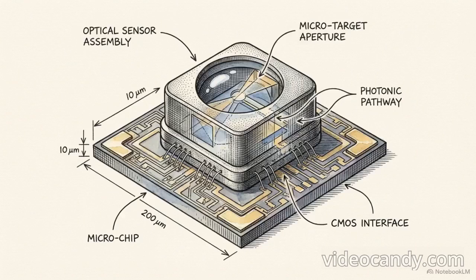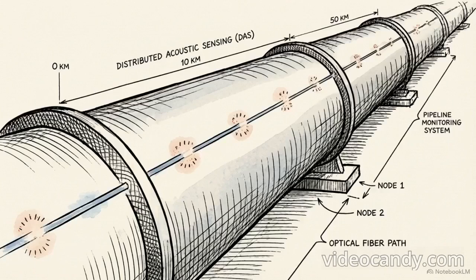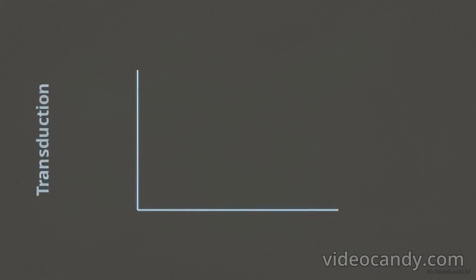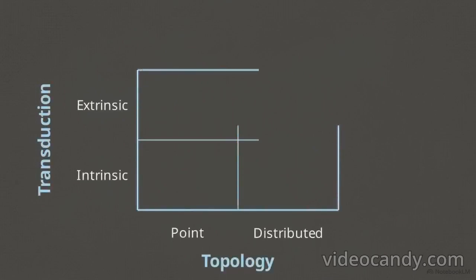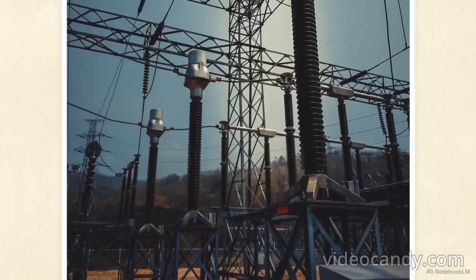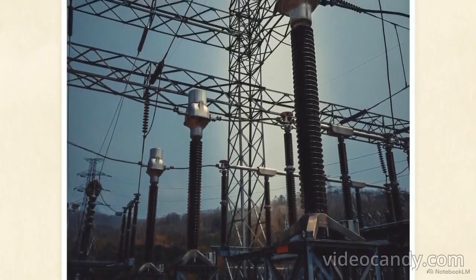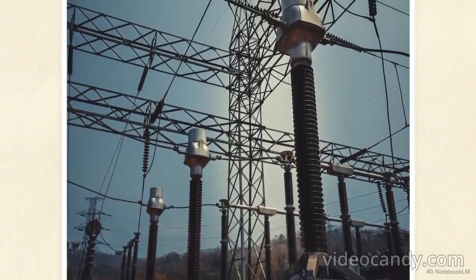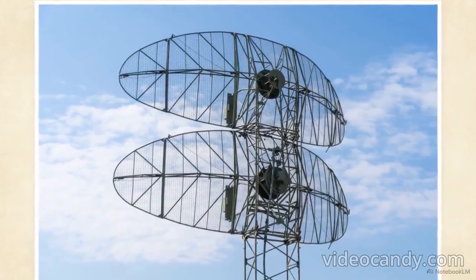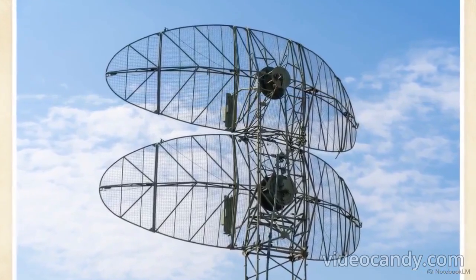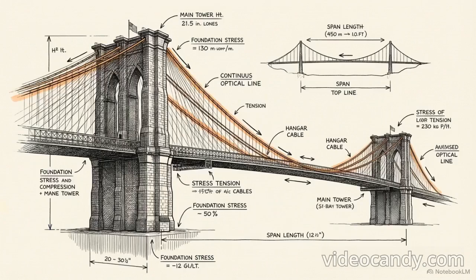In a distributed architecture, every single millimeter of a multi-kilometer fiber acts continuously as the sensor. By applying a processing technique called optical time domain reflectometry, or OTDR, engineers map continuous strain or temperature data along this completely unbroken path. Using these topological classifications, engineers can scale a network from a microtarget to continuous structural monitoring across tens of kilometers of pipeline, entirely without localized electronics. By crossing our two axes, the transducing approach and the spatial topology, we create a matrix that dictates real-world deployment. Consider high-voltage transmission equipment. To measure direct current while eliminating arc risks, an engineer deploys an intrinsic single-point architecture utilizing the Faraday effect. Conversely, supplying low-level power and transmitting sensing data within the intense electrical fields of high-powered antenna elements requires an extrinsic point-to-point setup.